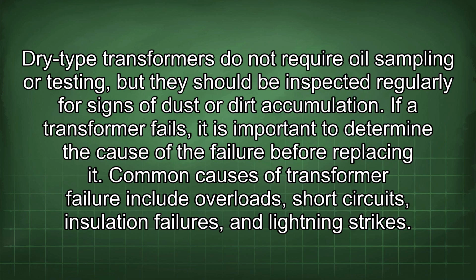Dry-type transformers do not require oil sampling or testing, but they should be inspected regularly for signs of dust or dirt accumulation. If a transformer fails, it is important to determine the cause of the failure before replacing it. Common causes of transformer failure include overloads, short circuits, insulation failures, and lightning strikes.